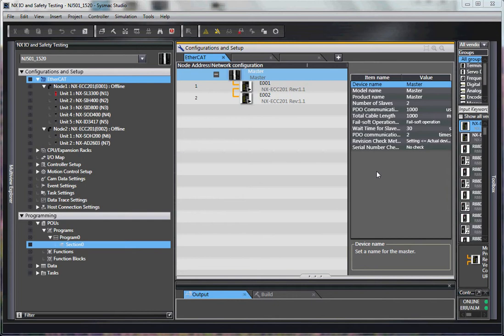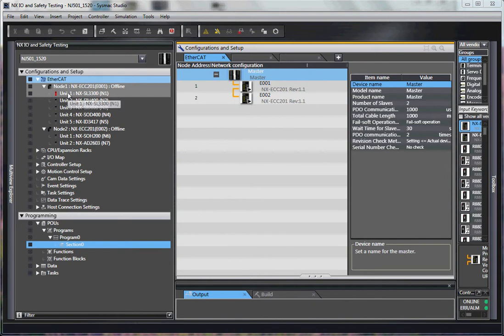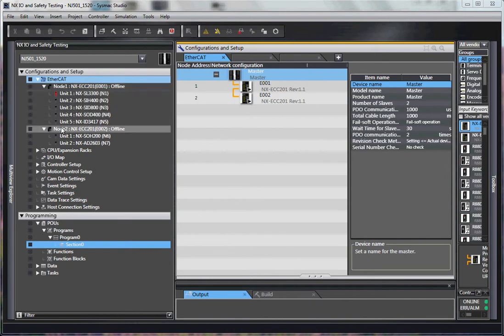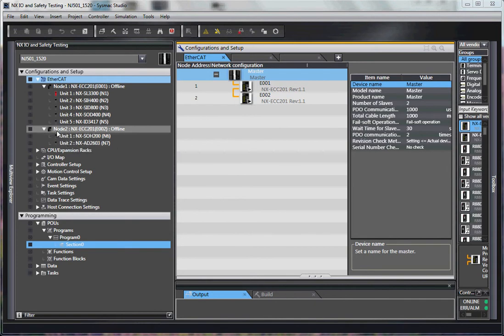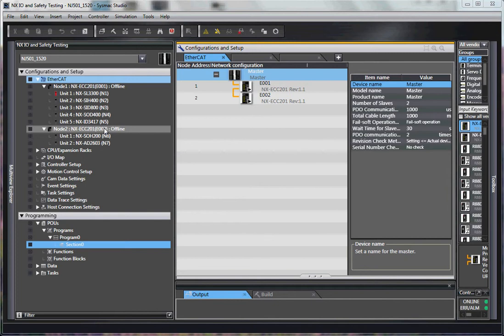In this example we have the safety unit in node 1 and some safety I.O. In node 2 we do have a safety I.O. card. We want to be able to disable this node so that we can rewire it, add some I.O. or whatever, do maintenance, without causing the safety CPU going into an error.